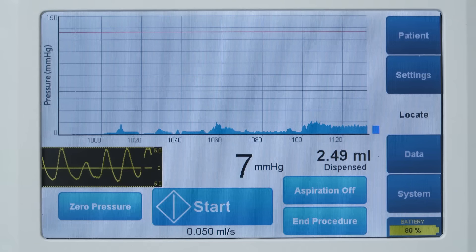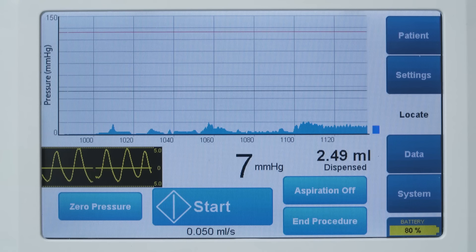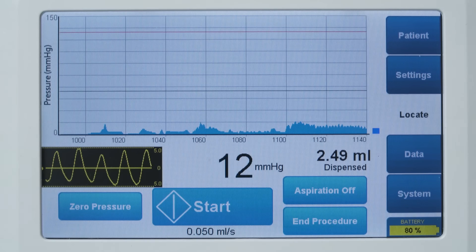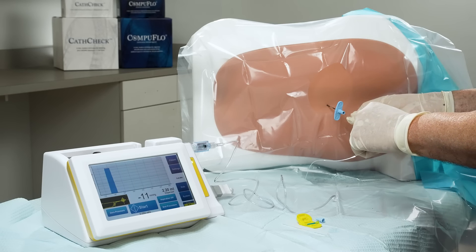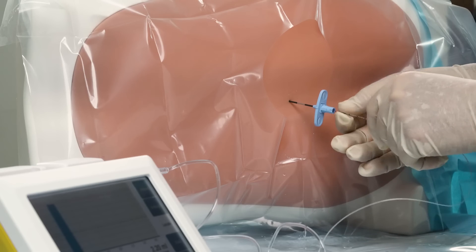Once the needle is inserted, the CompuFlo display monitors the pulsatile waveform in the epidural space by using the CathCheck Verification System. This system allows the clinician to confidently confirm catheter placement within 1 to 2 minutes.